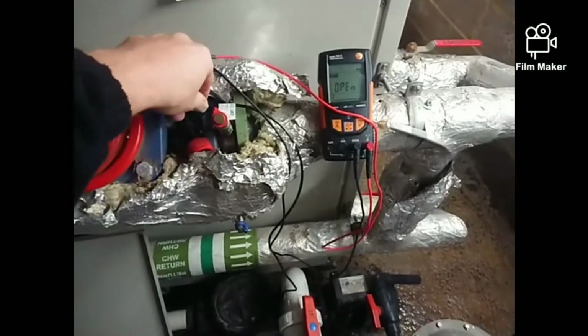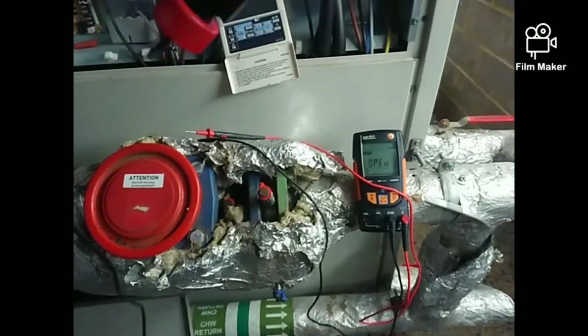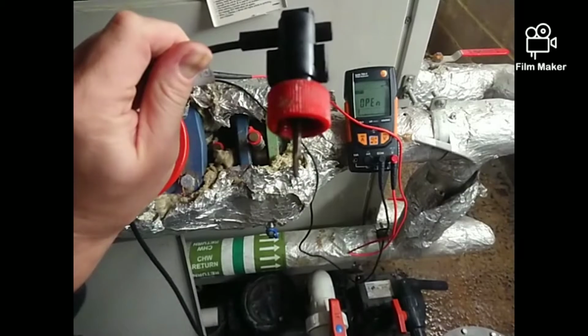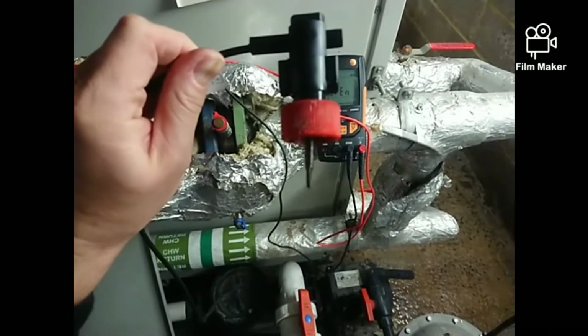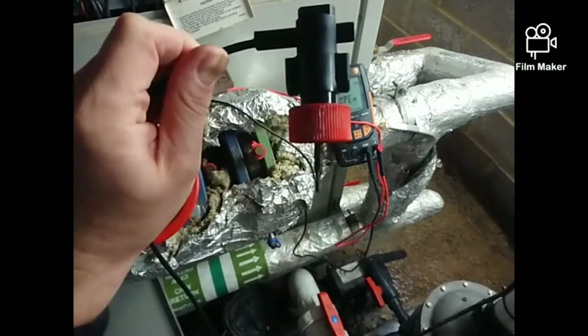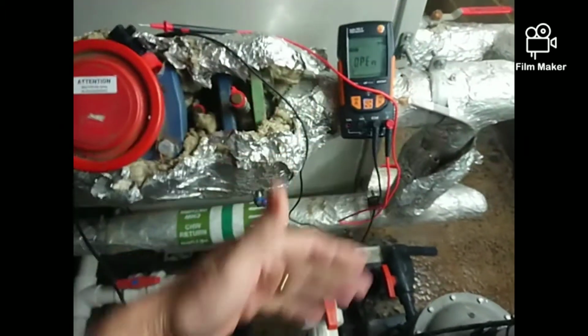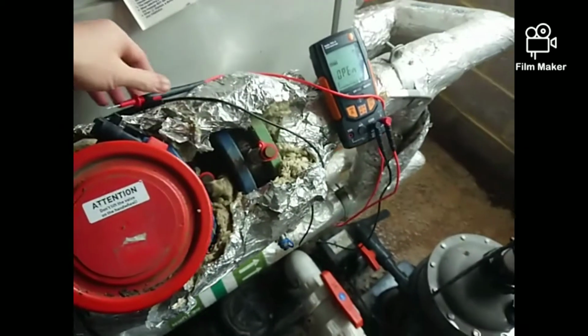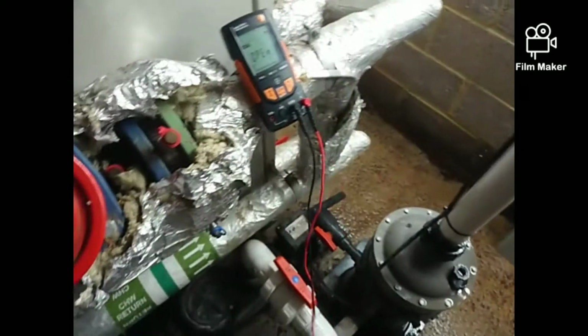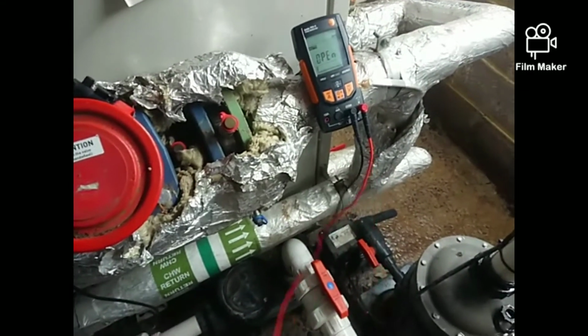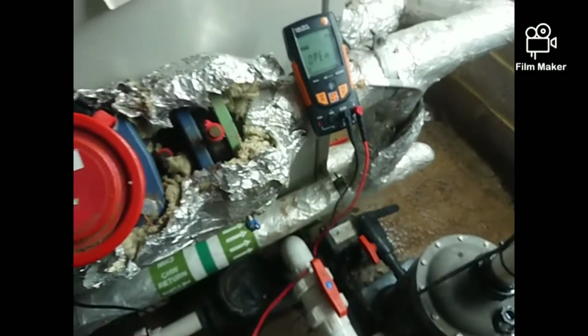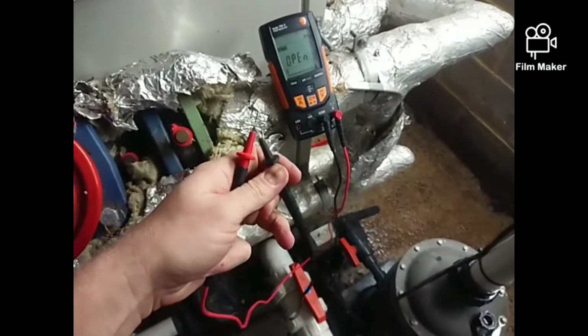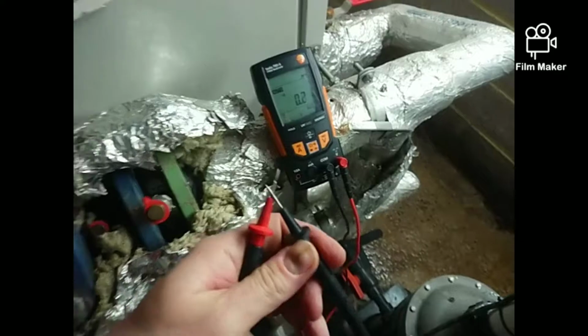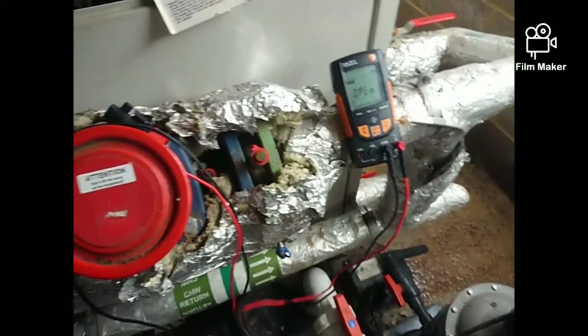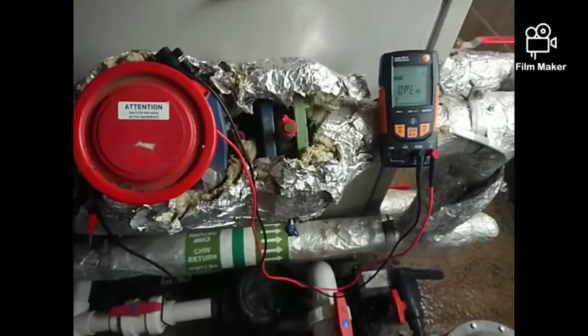Okay, we've removed the flow switch. Just so you know, this is what it looks like. All that is a paddle on the end. When that paddle moves left and right through the flow of the water, it makes or breaks the signal. So it is a simple open and closed contact, and to test it while it's in situ, you can just use your multimeter and a continuity tester to test across the terminals from the PCB. I'm not teaching anyone to suck eggs, but that is how you test it.